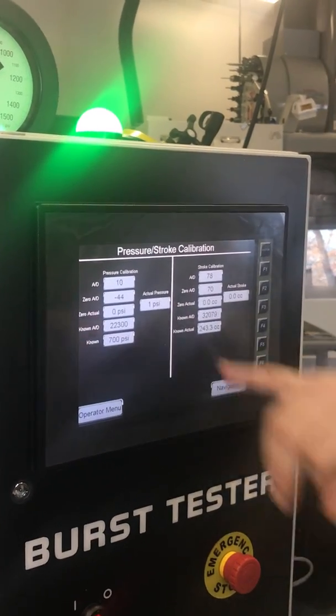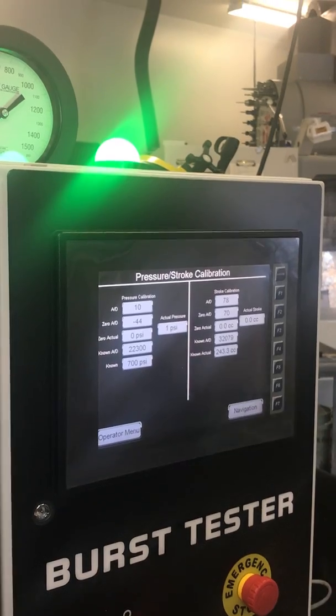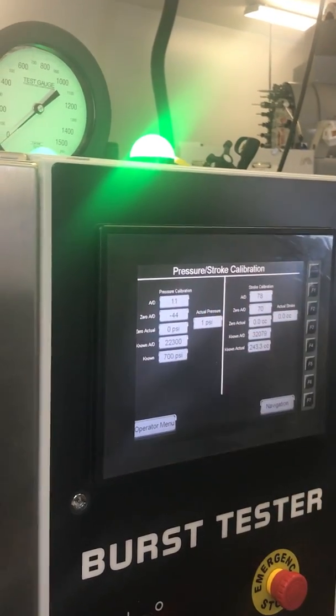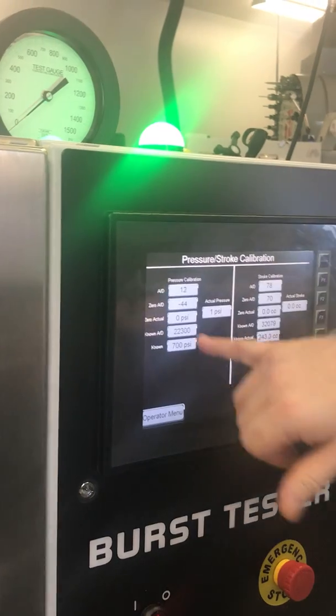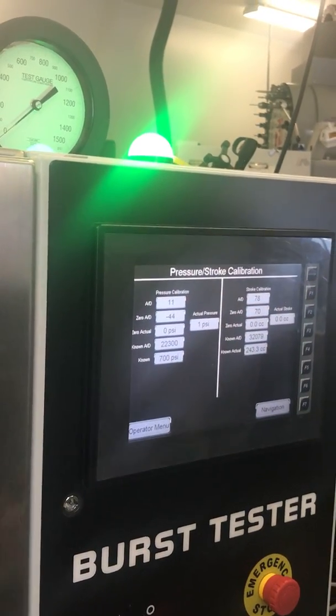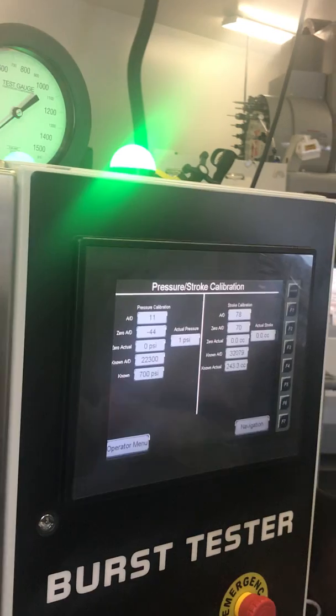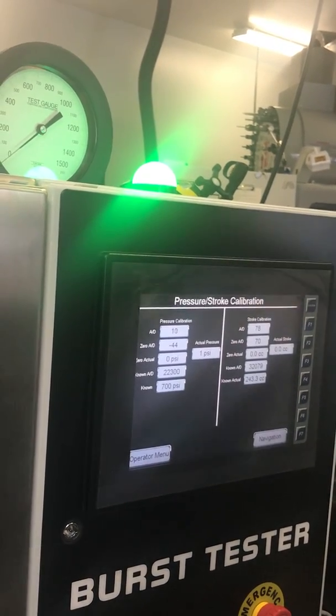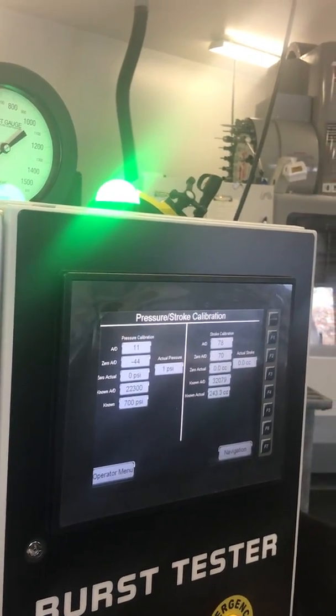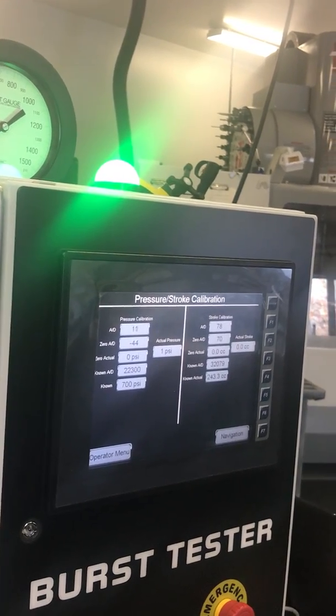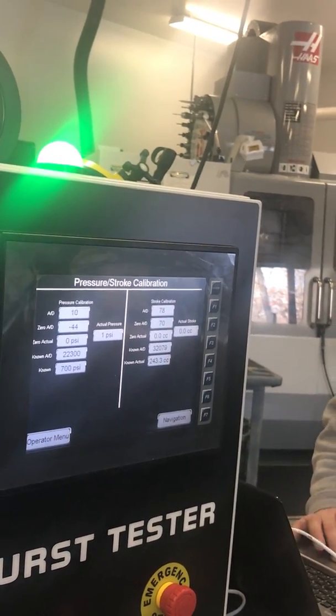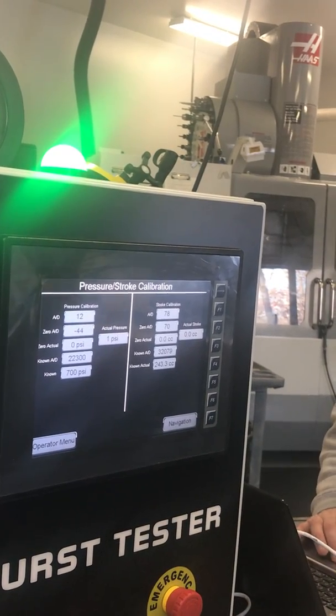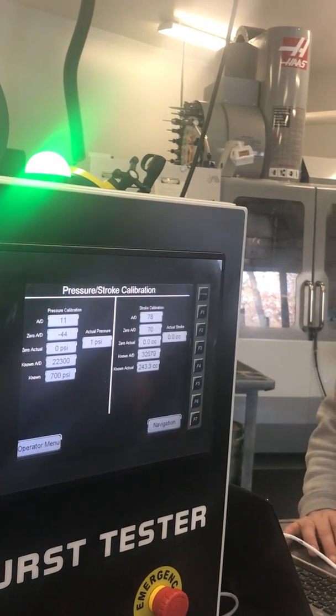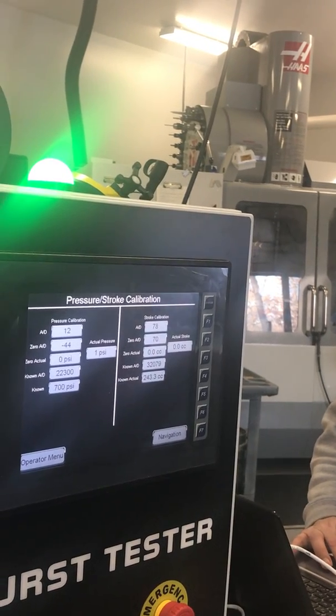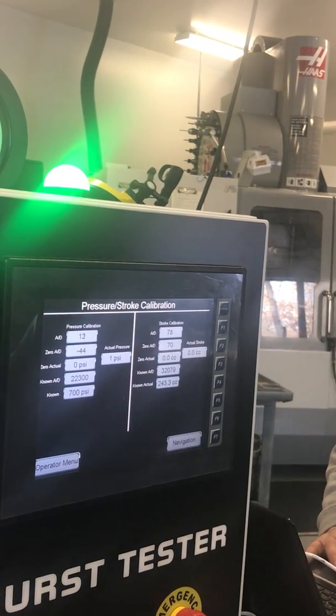I/O screen pressure calibration. So what we did is calibrated this. We have our analog to digital conversion. We took this down to 0, and we were setting at about a negative 44. So by just opening the whole system up, what happens is we're giving it an analog voltage. Like 0 volts is 0 pressure. So what is 0? I mean, really, what is 0? When this voltage goes into the PLC, it tries to convert it to a digital number. And I think Corey's working between 0 and 32,000. So we're going to cut 10 volts into 32,000 pieces.